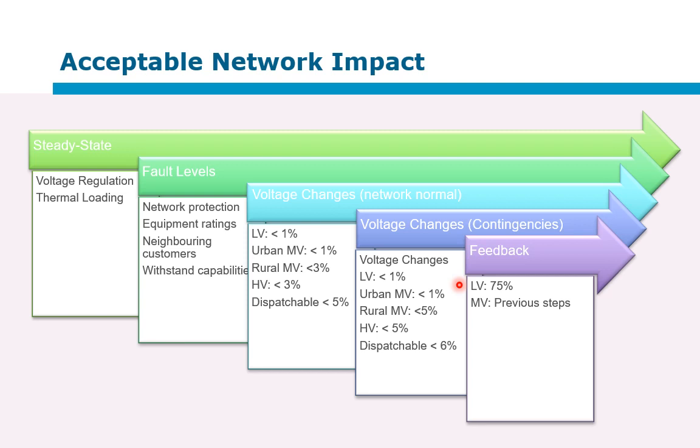Distribution transformers are not designed for harmonics. So if you consider a higher feedback into an LV network, discuss that potential impact with a transformer supplier. At medium voltage, one would look at all these impacts probably at a higher voltage level up to make sure that the entire network remains operationally in a good condition.